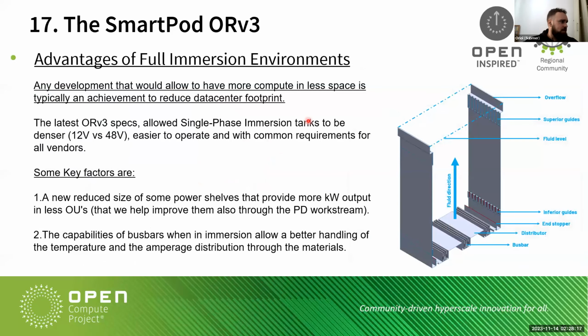As a tank manufacturer and provider, Open Rack version 3 provided a very good advancement, increasing the voltage from 12 to 48 and 54. This voltage was also available in Open Rack version 2, but no one was actually using it. Now server vendors are installing power distribution boards inside the servers to reduce from 48 to 12, 5, or 3 volts, making current distribution over the busbar more efficient.